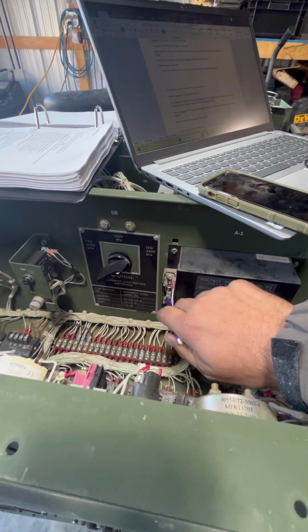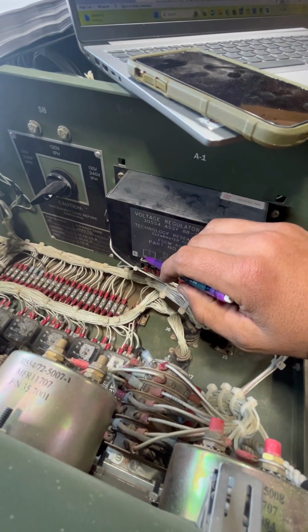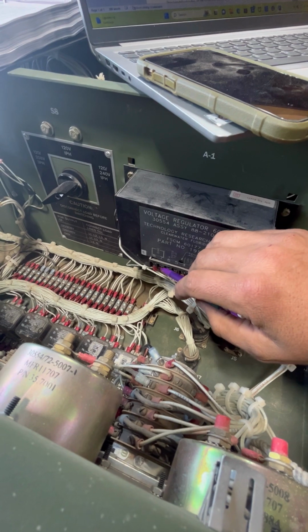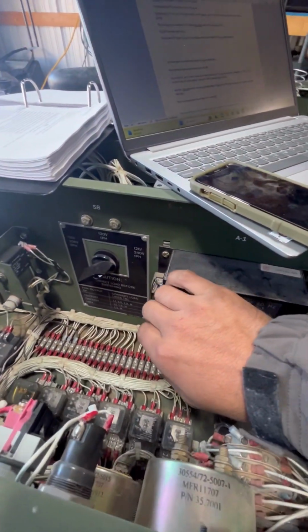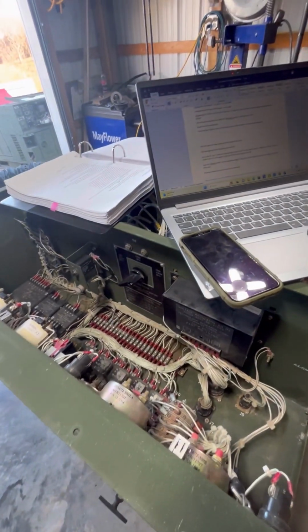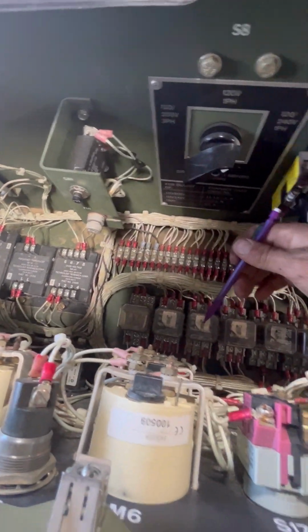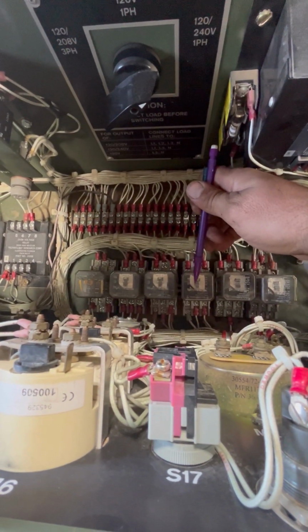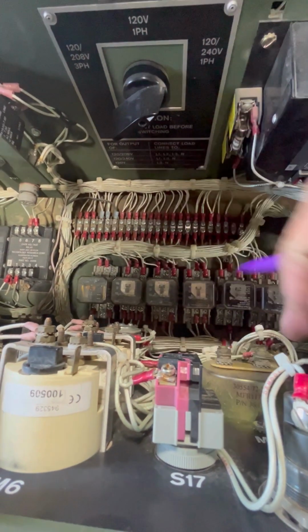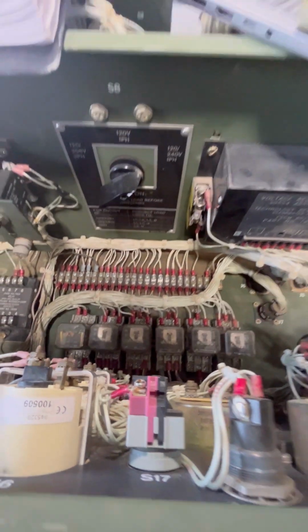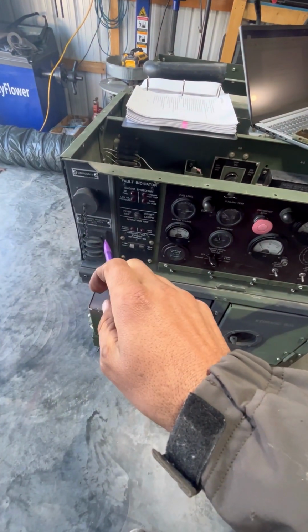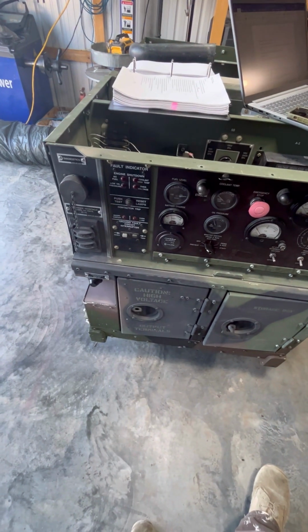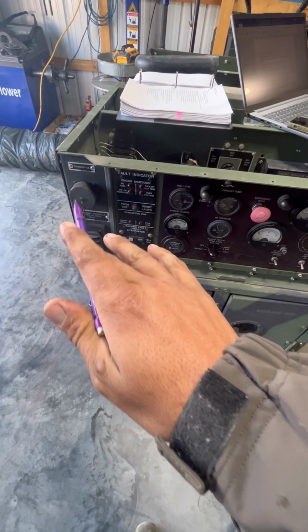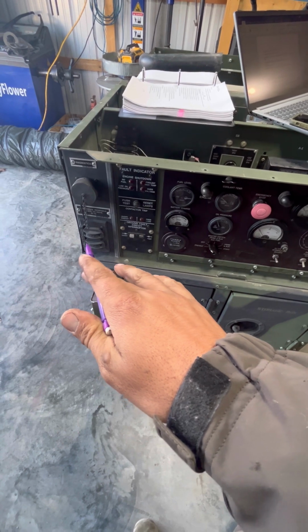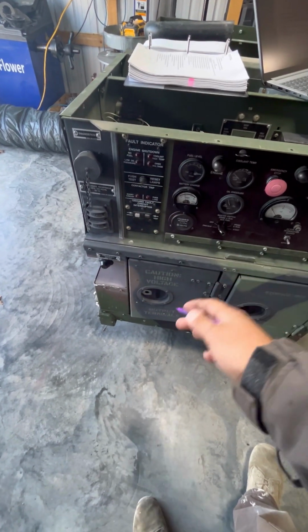Then I checked fuses, simple things. I checked the quad fuse right here. You can just jump across terminal 8 and 7 with a multimeter and verify that you do have continuity, and typically if you do, then your fuse is good. I swapped the K15 relay, this relay, and the K16 relay to verify that I did not have a bad relay. And I also verified that I had power at my convenience receptacle right there, which typically means the generator is producing power, you're just not getting it at the main lugs.